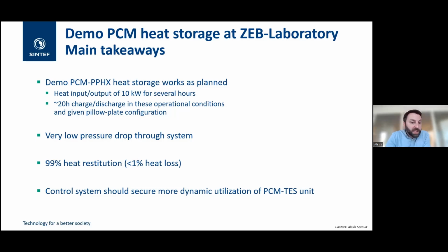We have a pillow plate configuration for the heat exchanger inside. When we designed it, we could adjust how we configure the pillow plate to get more or less output, reducing or extending the discharge and charge time. This is a parameter we can play on. In this case, we aimed for 15 to 20 hours charge discharge for a full cycle.